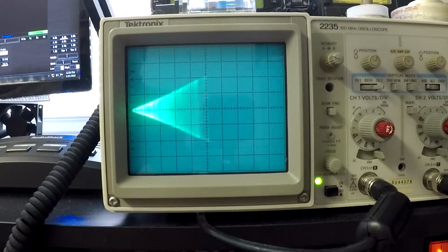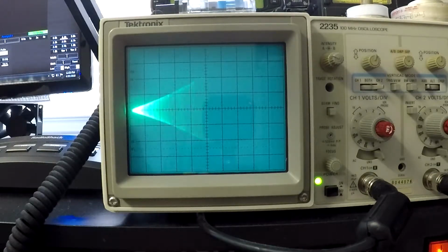At any rate, you can see in the trapezoid, it definitely does not look like straight lines going from the small end to the big end of each side of the trapezoid. But this is the best you can achieve. I can actually go in here and try to turn the tuning and load. You can see I just adjusted it there. There's nothing I can do to get that thing to straighten out and provide a linear looking trapezoid. So again, this is what you have with 200 milliamps on the two bias G1 and G2 and 8RWS.